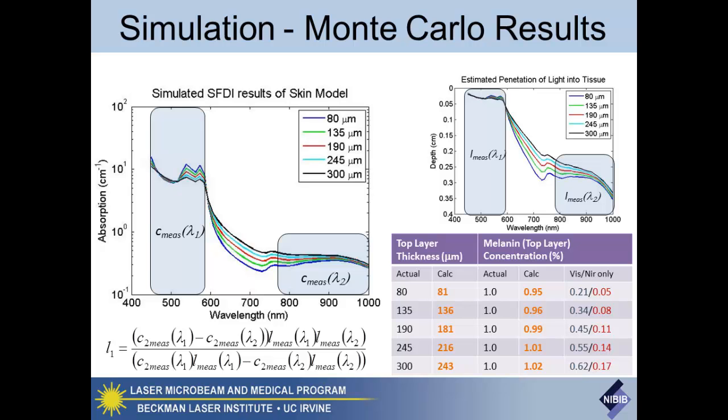I mean, the actual recipe, there's a lot of different factors going into the fabrication. So you will have target optical properties when you fabricate the silicone phantoms. What you actually get when the phantom cures is not necessarily exactly what you put in. So the accuracy of dyes and scattering, because you're usually talking about titanium dioxide, which can aggregate. So you never really know exactly what the scattering properties, what the average particle size will be when you fabricate these. So there's a certain limitation to that.